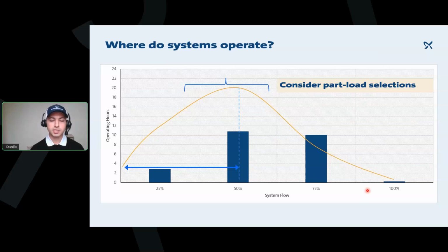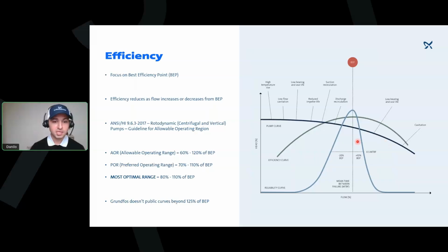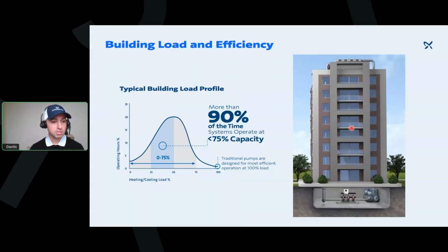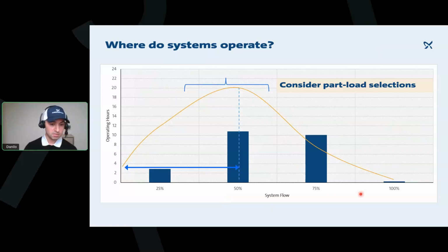Why are we still seeing equipment today, if you walk into a mechanical room, why are those equipment oversized? Because many engineers were still sizing pumps for the 100% load. So what happens here is, if I go back a few slides, right, when we look at this, we're selecting the best efficiency point for the 100% load. Do we spend any time in there?